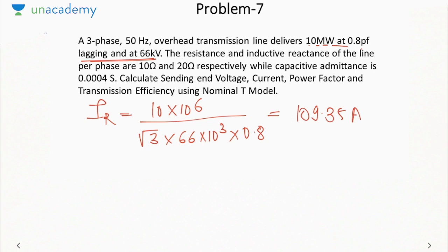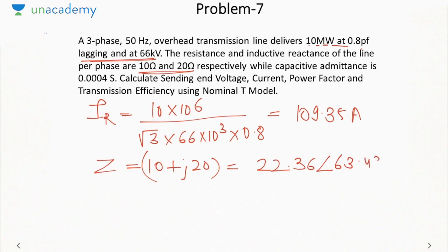Let us move forward. The resistance and inductive reactance are 10 and 20. So that is 10 plus j20. So expressing it in polar form, it will be 22.36 angle 63.43 degree ohm. Capacitive admittance is 4 into 10 raised power minus 4 and angle will be 90 degree Siemens. Okay. We need to find sending end parameters like voltage, current, power factor and efficiency using the nominal T model.